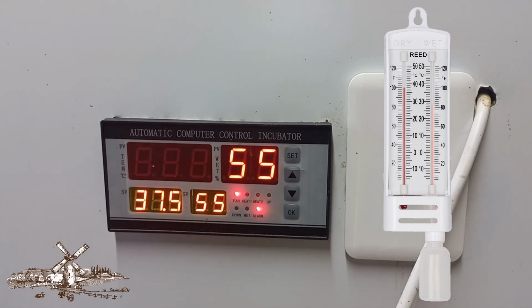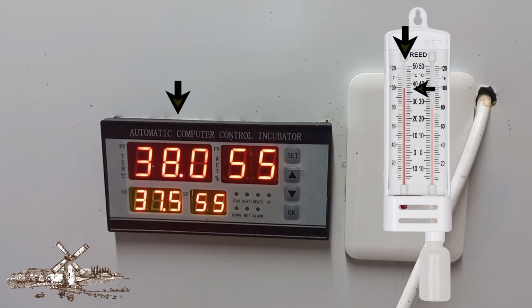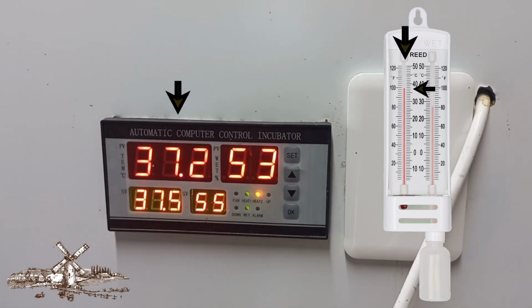That should kick in. And the controller will now slowly bring your temperature back down to what 37.5 is based on its new measurement. Now, what we would expect to see as well is the temperature on our dry thermometer should also come down together with your digital controller. And unless your controller has a problem, we would expect that the controller's temperature will settle on 37.5, and we would expect that the dry thermometer on the right hand side also drops down to 37.5, which you can see on the thermometer now matches.